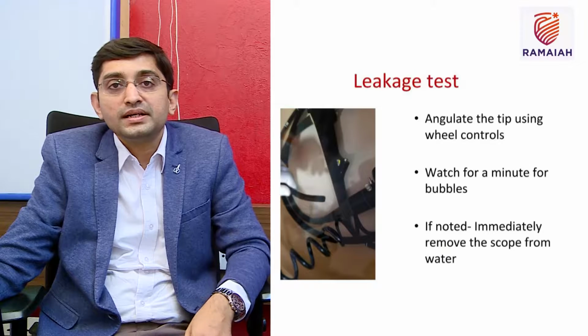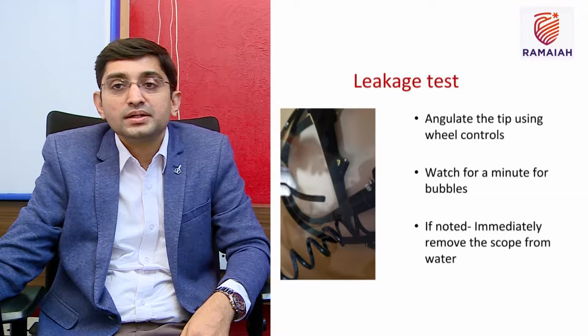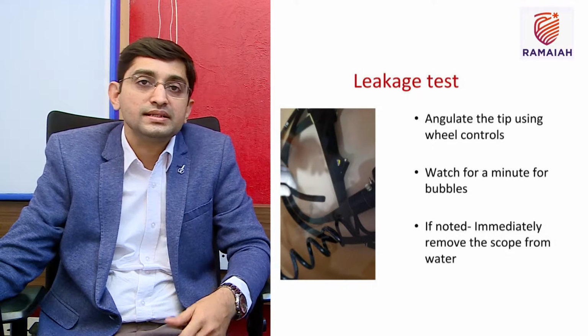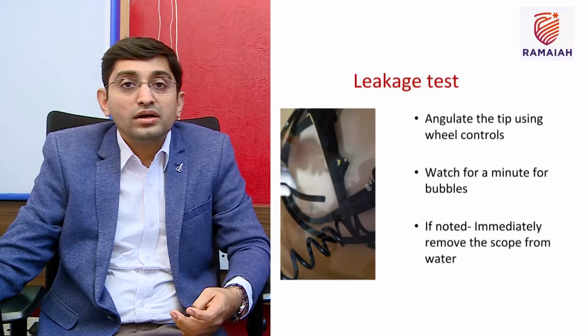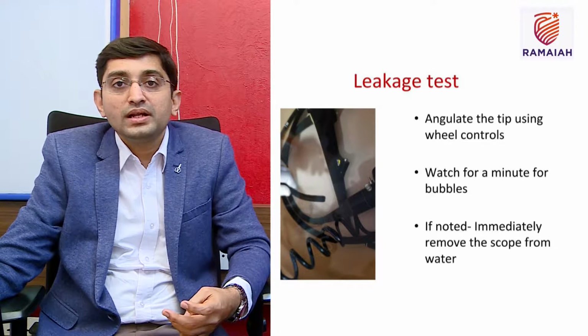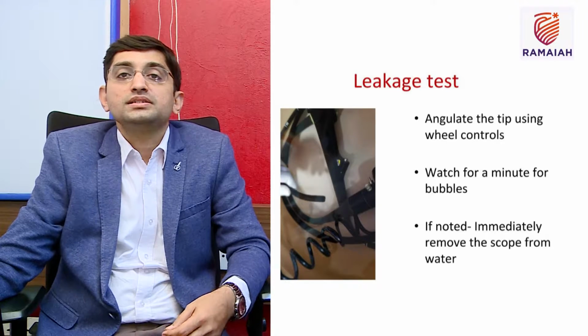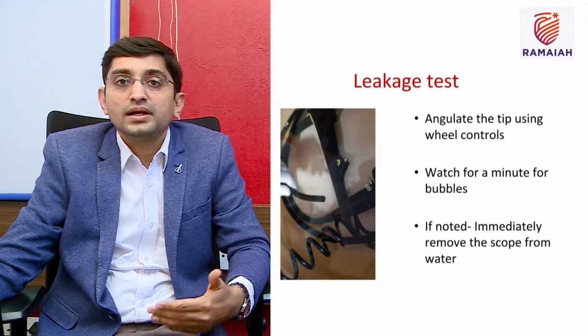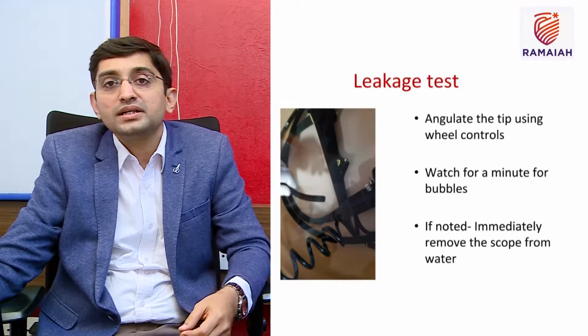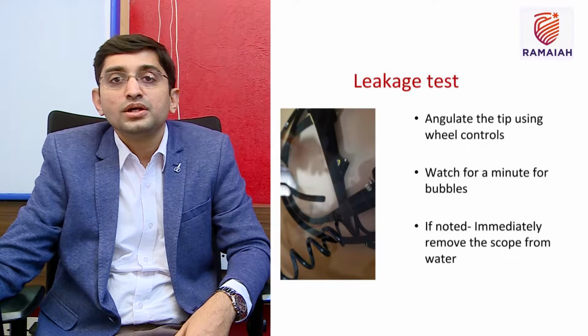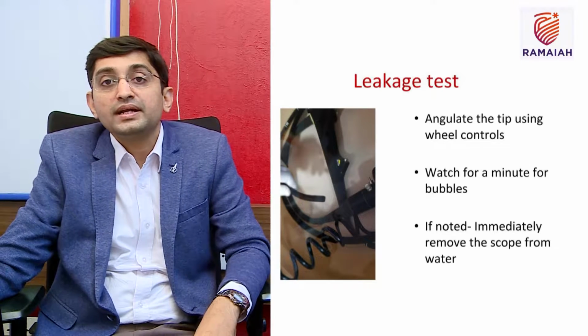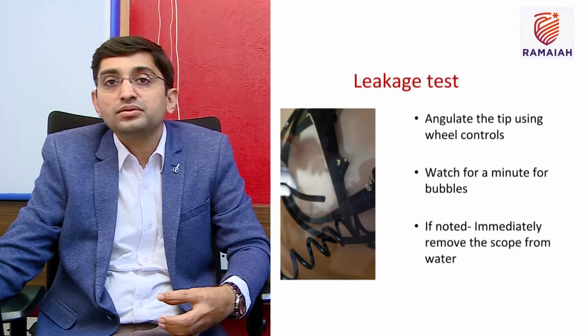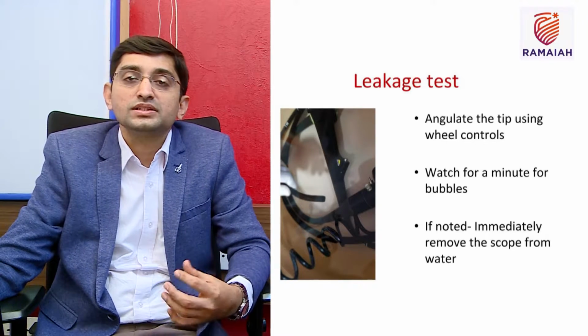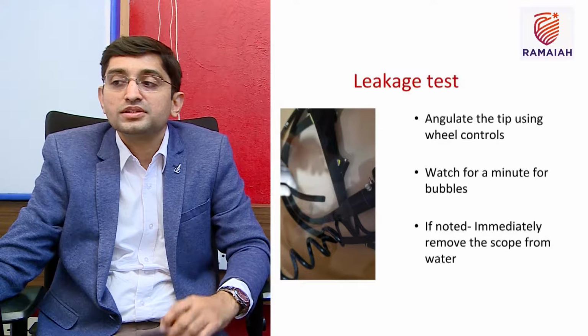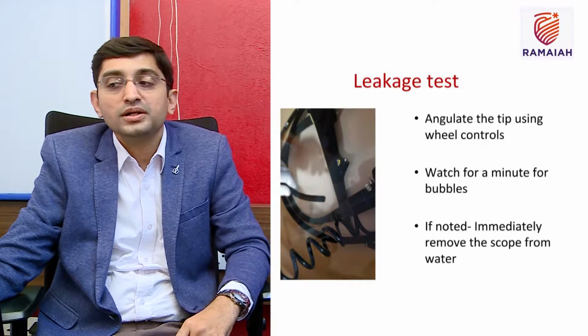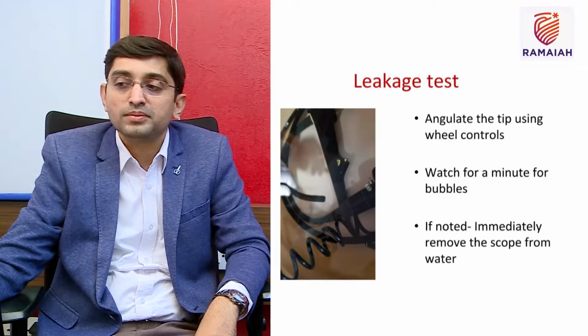Once we immerse the entire scope within the water, if bubbles are coming, that means there is a leakage. We need to angulate the scope, using the big wheel up and down, so that any small leaks can bubble out and the leakage test will be positive. We should always dip the scope for the entire minute, for the air to accumulate within the scope as well as for the bubbles to manifest. So it's always better to keep it immersed for a minute and then watch for the bubbles.